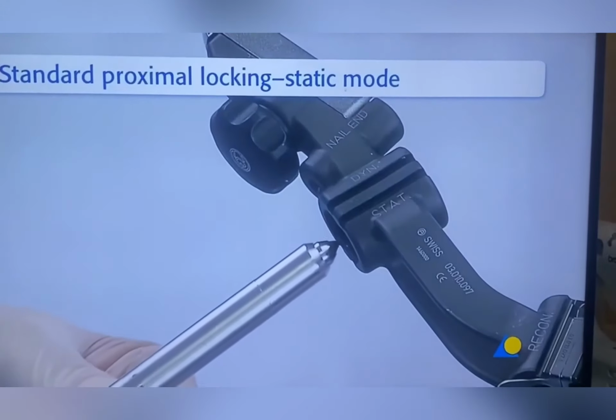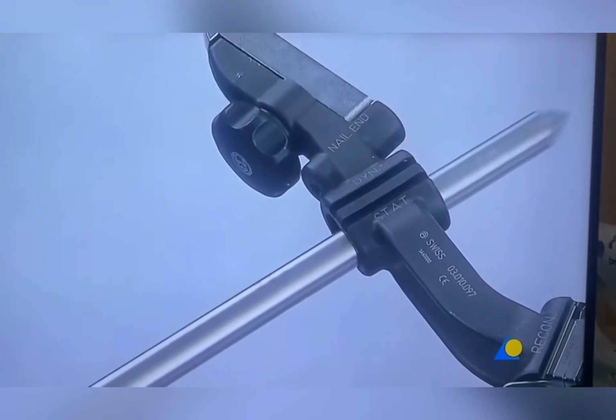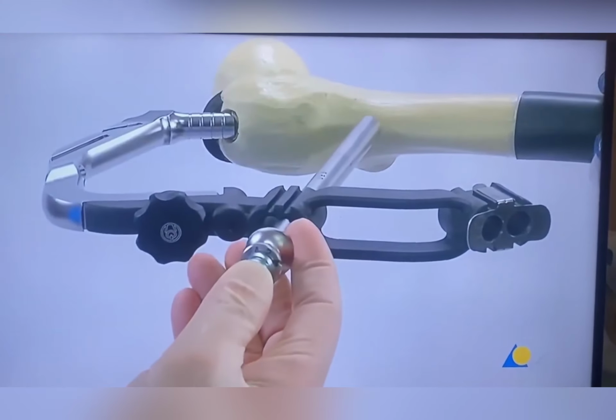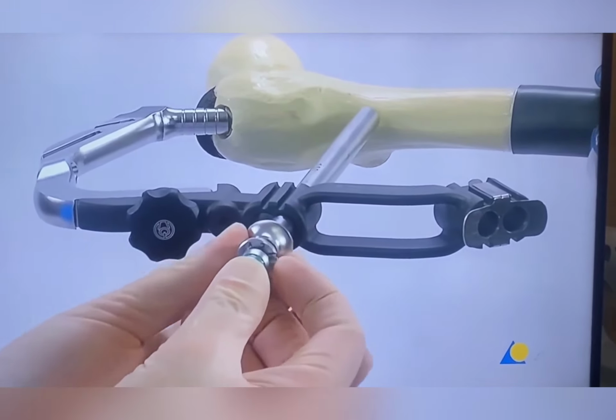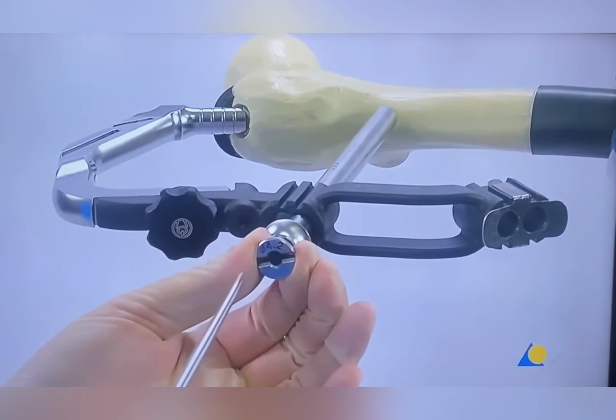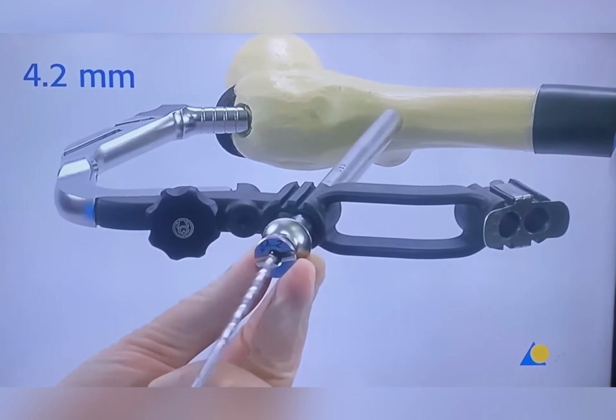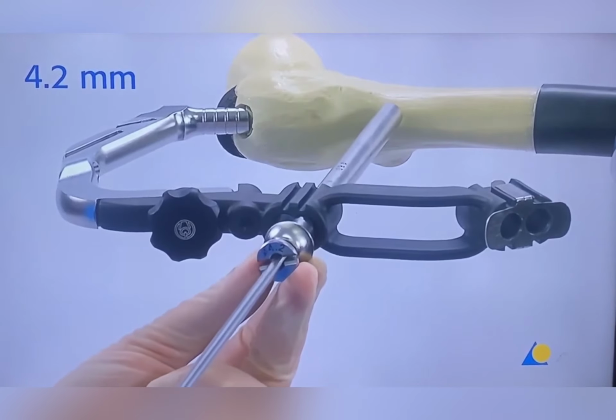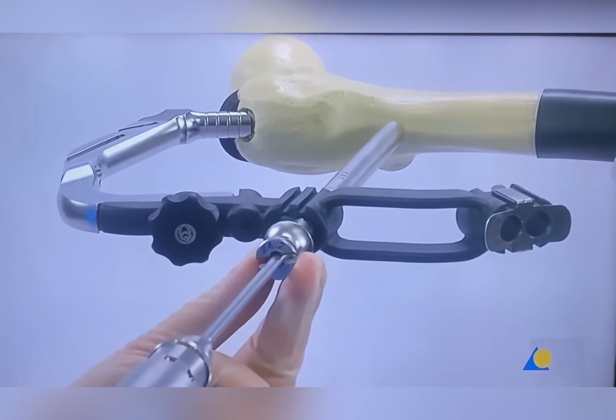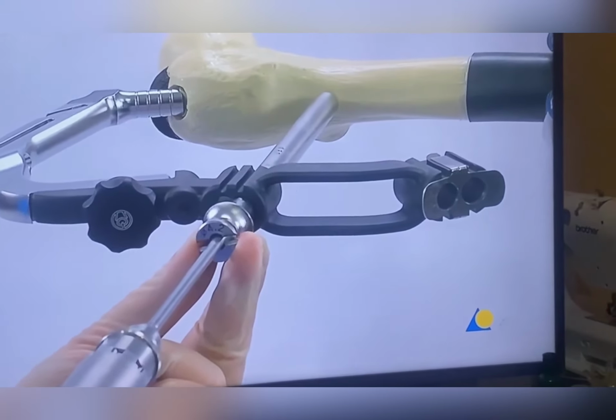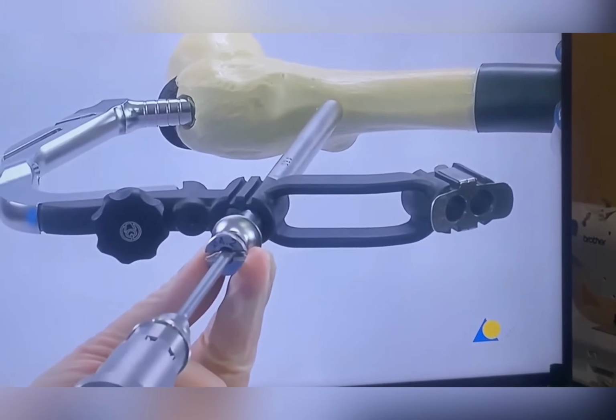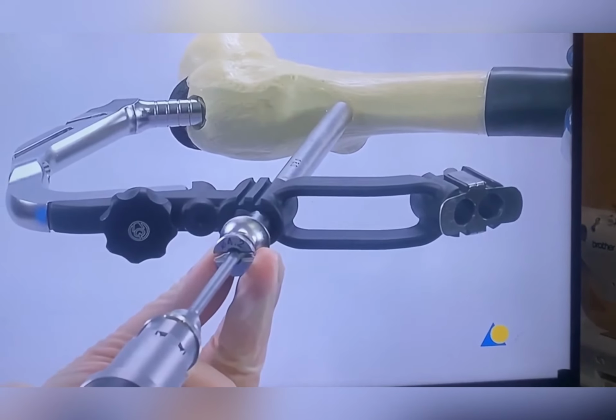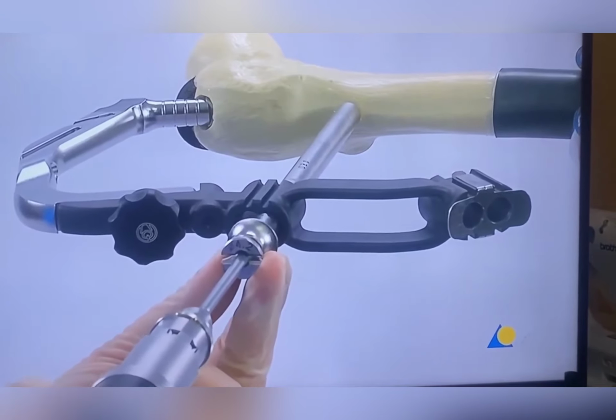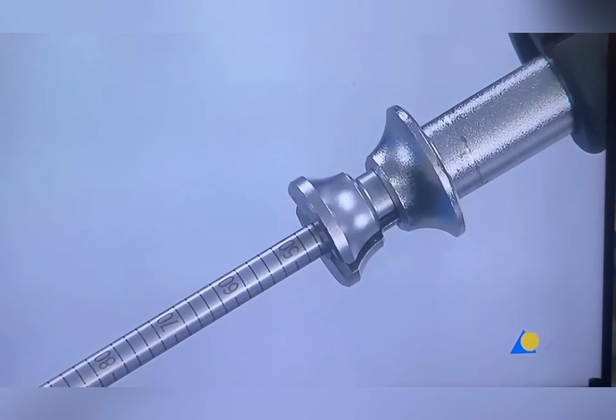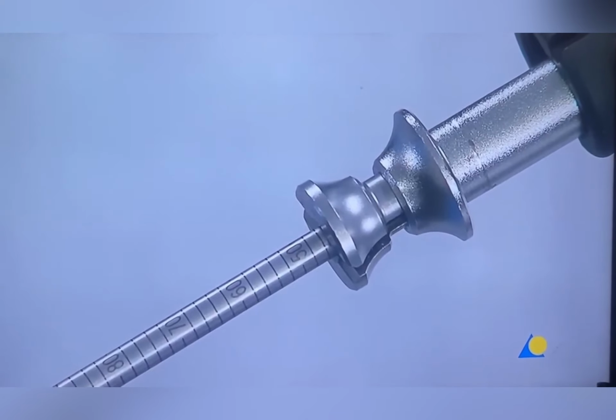And this time we will use the standard proximal locking static mode for the femur fracture of the shaft, using the silver drill sleeve with a green color label and using the 4.2 mm drill bit with the same green color label. This is always guided with a C-arm to check the depth and the position of the drill bit and the screws. Check the size in the calibrated drill bit.